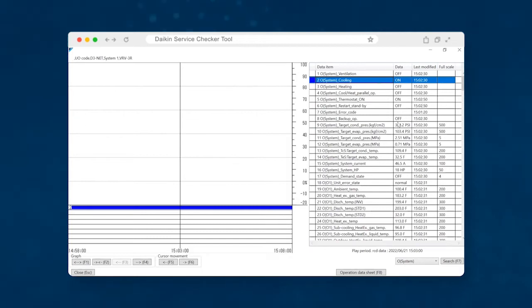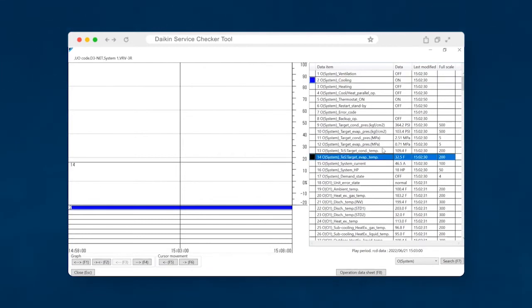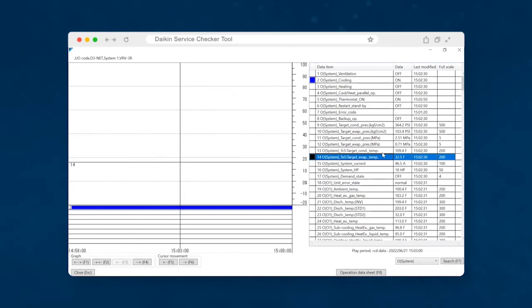The next thing that you'll want to look at is the target evaporator temp. So this is essentially the target evaporator temperature that the system is trying to achieve. So this is a pressure value that's been correlated to a temperature, just like looking at your manifold gauge set where it has the pink range underneath your pressures on 410A. This is exactly what that is.